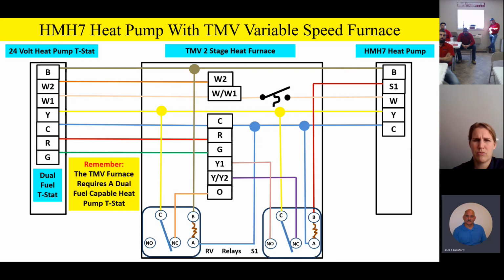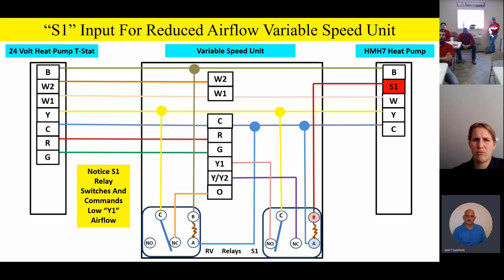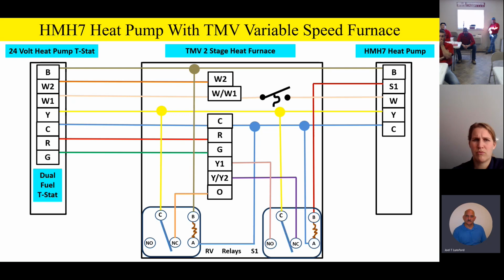But now watch this on those furnaces. Again, remember that furnace has to have a dual fuel configuration on the thermostat. So just please remember that. But now let's go back and take a look at a variable speed unit switching. So let me do that animation again. This is going to be the switching now of the airflow.